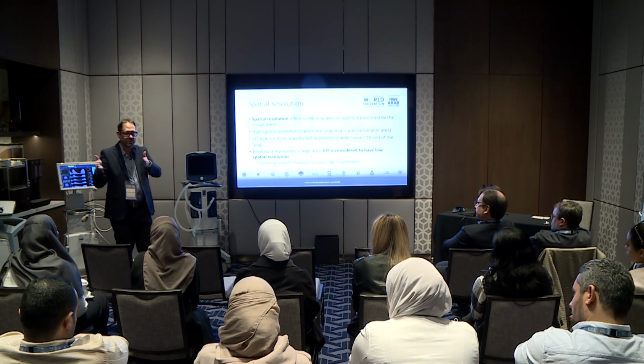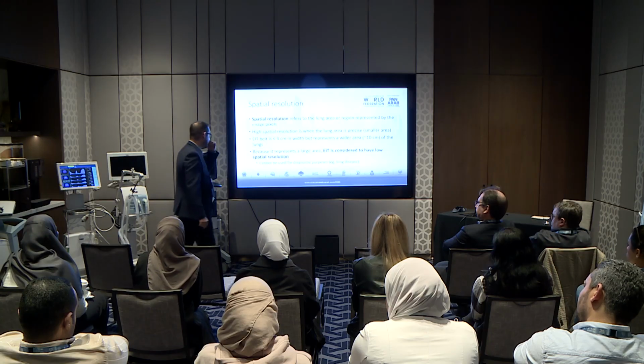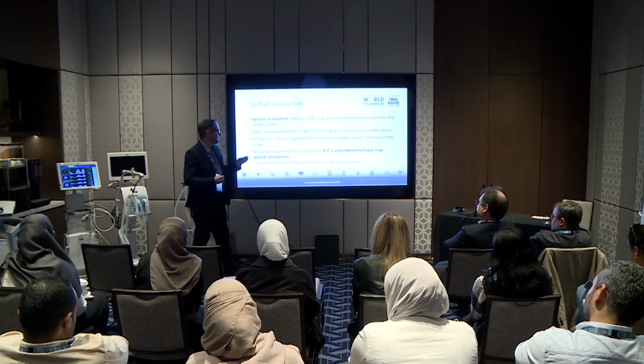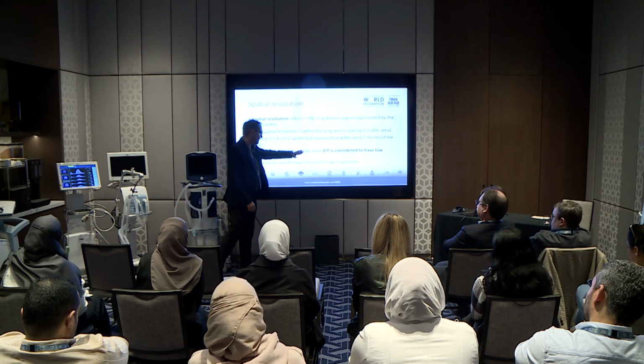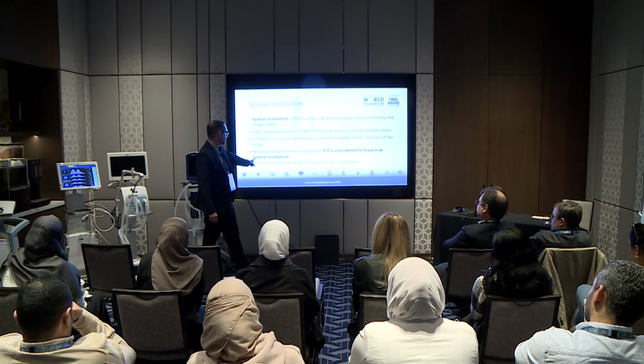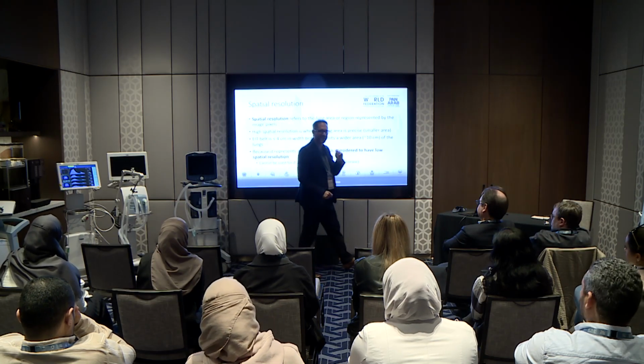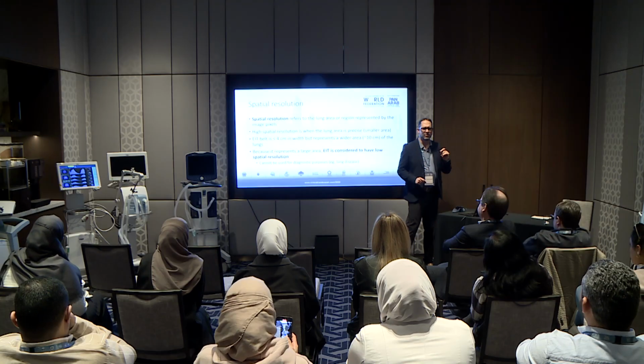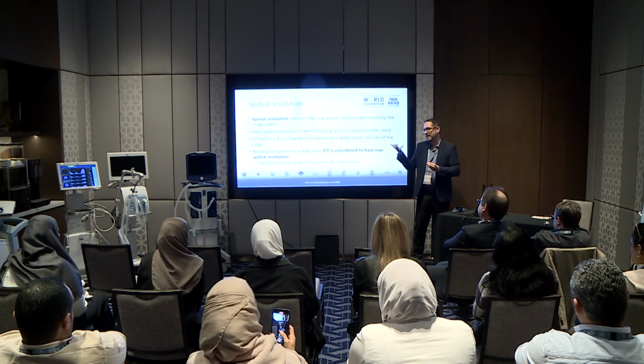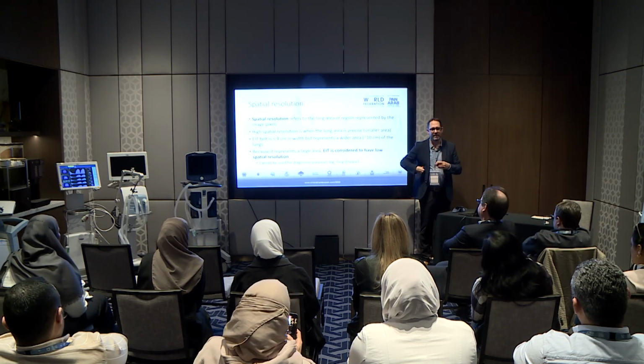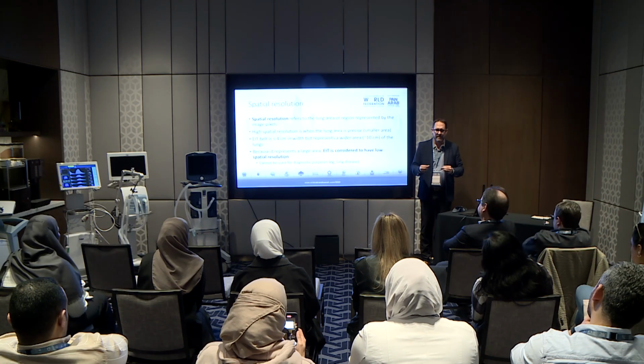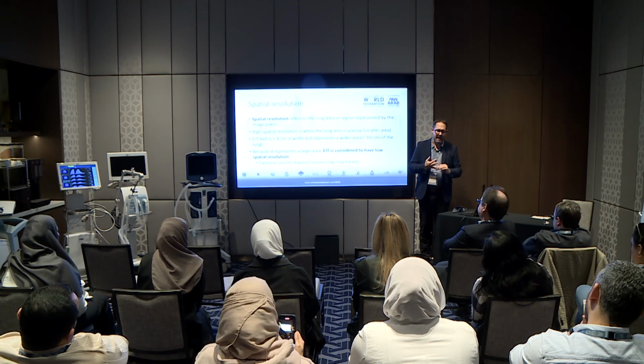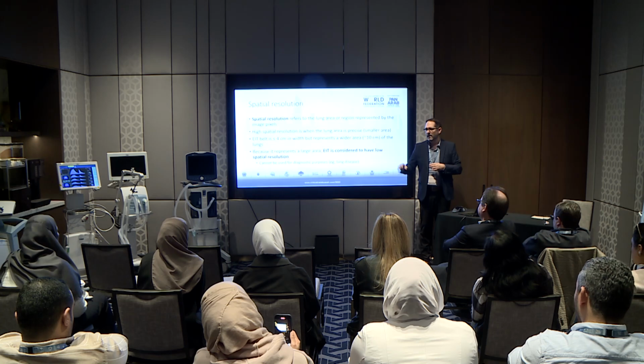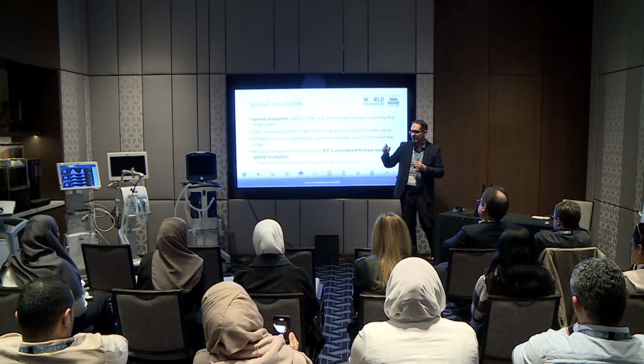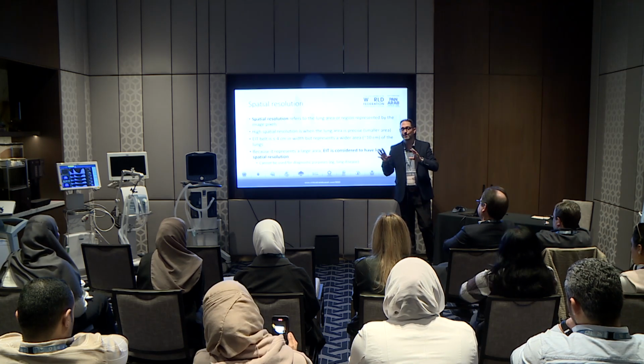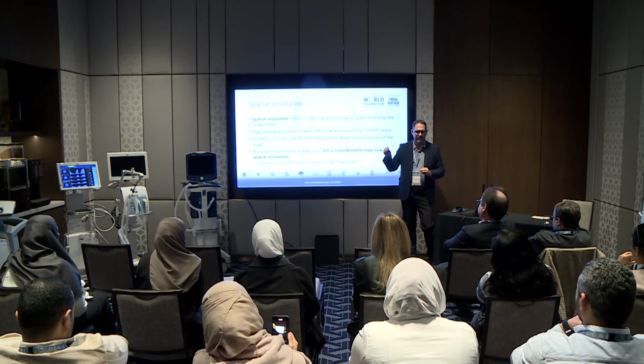Like a CT scanner, you move the patient through the scanner. So CT scanners have very good spatial resolution. EIT does not. It has very low spatial resolution. So for this reason, it cannot be used for diagnostic purposes of lung disease, tumors. You can see maybe that ventilation is not occurring somewhere, but the machine can't tell you precisely if it's consolidation, if it's collapse. It just knows that it cannot ventilate. There's things that you can do with the device that will tell you if it's likely pleural effusion, but we can't diagnose things properly with that.